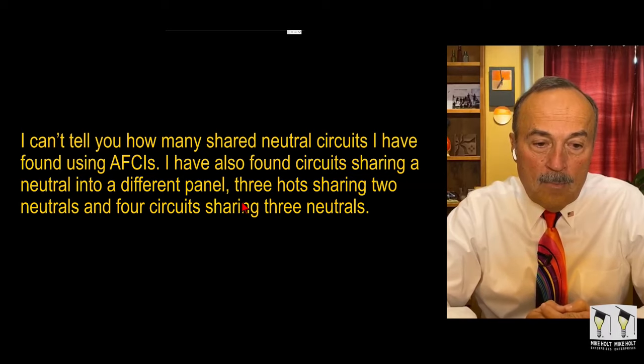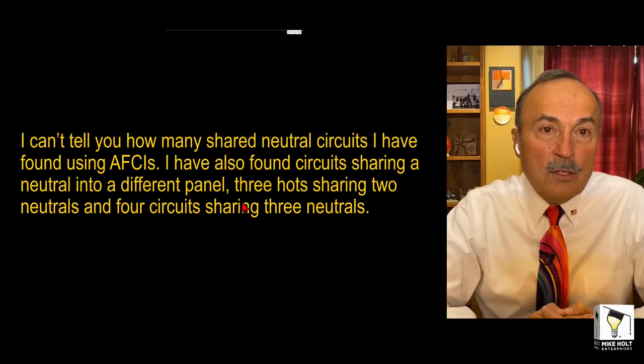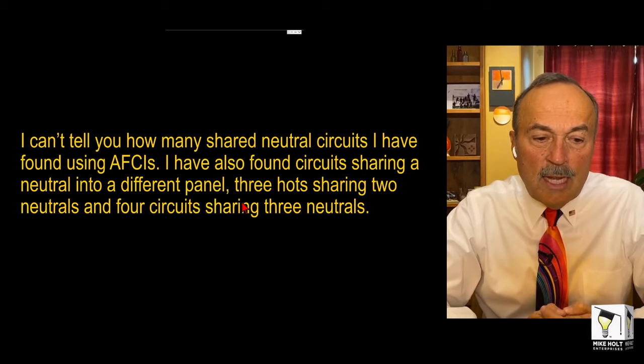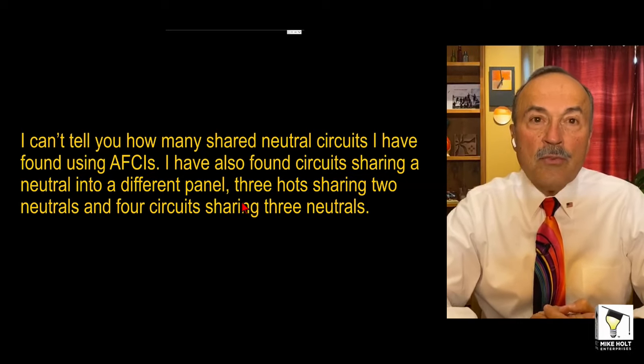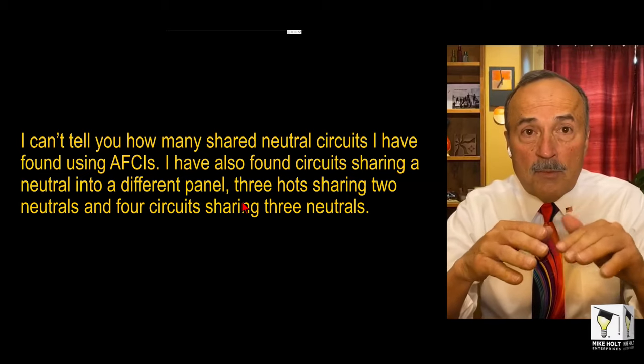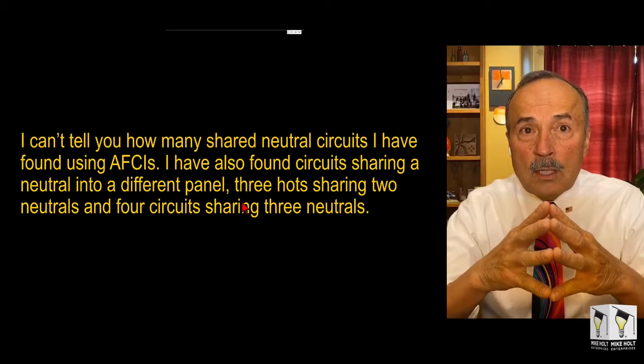He says, listen, I can't tell you how many shared neutral circuits I have found using AFCIs. I've also found circuits sharing a neutral into a different panel, or three hots sharing two neutrals, and four circuits sharing three neutrals. Brian and I and some other team members have actually done some work watching electromagnetic fields in a particular person's house. We found out with a milligauss meter, I'm not saying it's causing cancer or not, or causing people to go crazy or not, I don't know. All I know is that you can easily remove the EMF fields of miswired applications by putting dual function breakers on every single 15 or 20 ampere circuit in a dwelling unit.